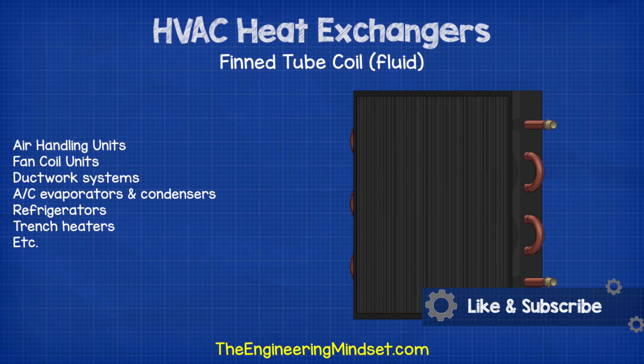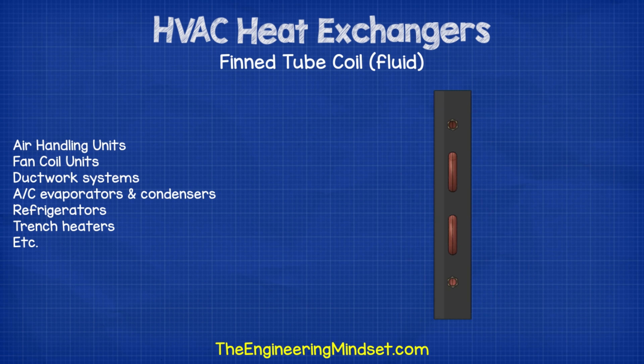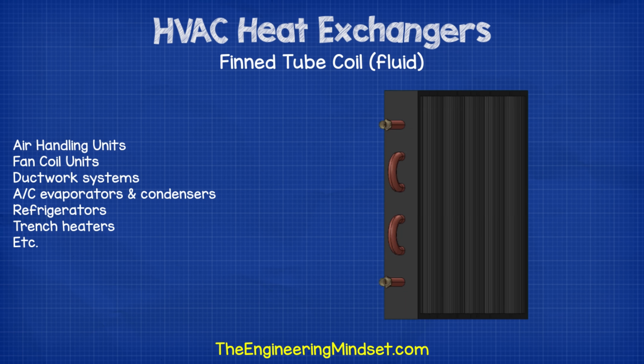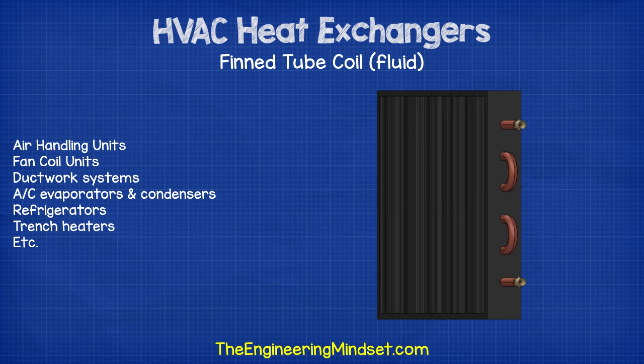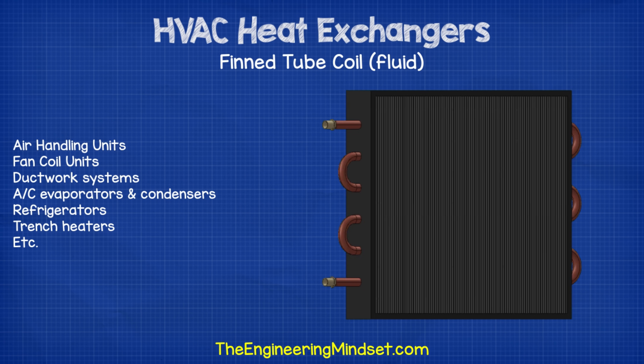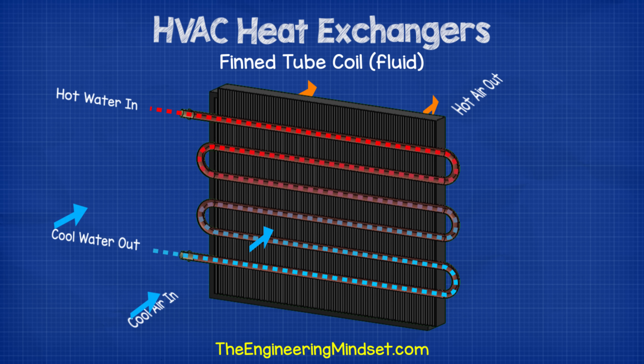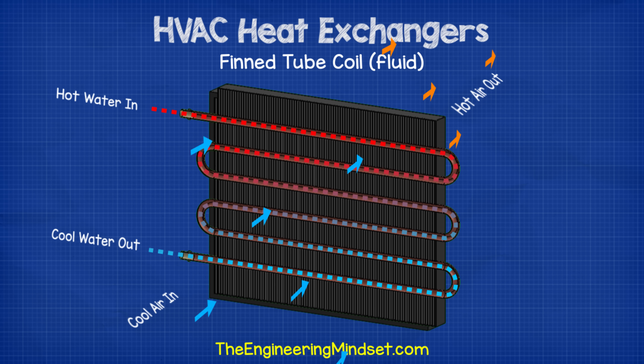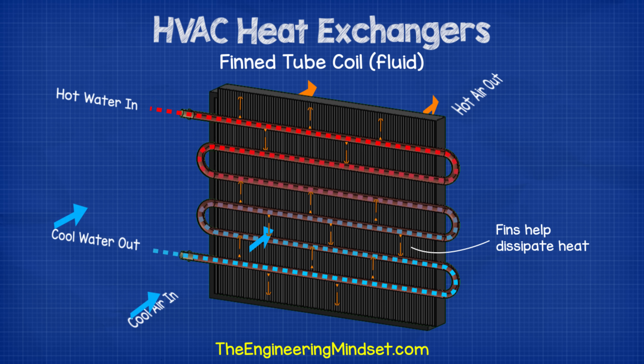Finned tube coil heat exchangers — often referred to simply as the coil, e.g. the heating or cooling coil — are extremely common. You'll find these in air handling units, fan coil units, ductwork systems, evaporators and condensers of air conditioning systems, on the back of refrigerators, in trench heaters, and more. Water, refrigerant or steam usually flows through the inside and air flows on the outside. The fins connect between all the pipes, sitting in the path of airflow, and act as an extension to the surface area of the pipe to help pull heat into the air.